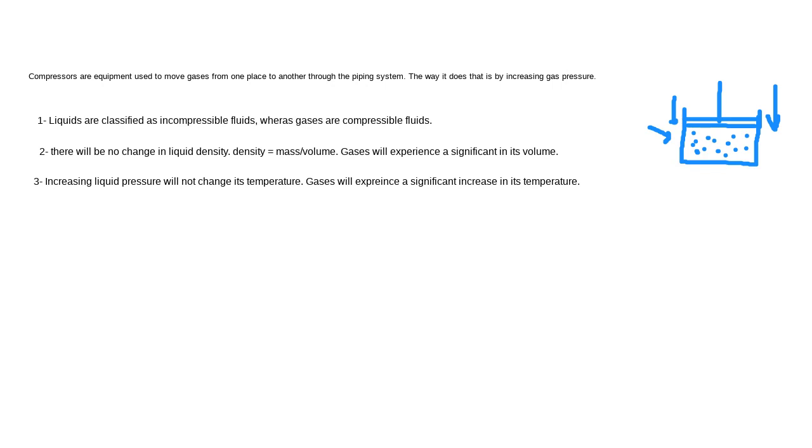That's why in compressors, guys, measuring the temperature at the suction and at the discharge is very, very important, okay, to determine compressor performance. عشان نحكم على أداء الكمبرسور، أحد أهم الأشياء لازم أراقبها اللي هو السكشن temperature والdischarge temperature. جميل. هذه أبرز الفروقات يا إخوان اللي تشرح الفرق ما بين الليكويدز والجازز. جميل.